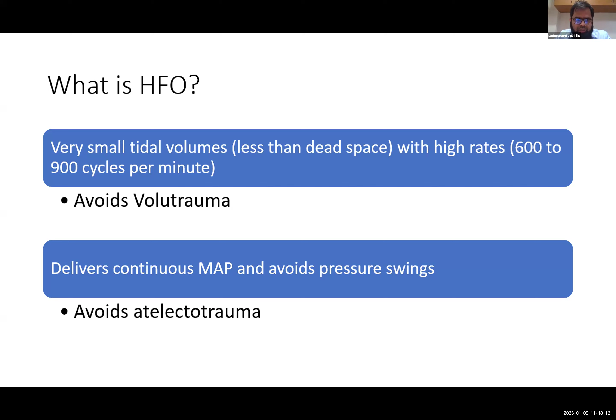So, the basic design and how it works. This is the basic design of the SensorMedics, but now a lot of ventilators are available, with different mechanisms. Here you can see one piston. One ventilator apparatus will give the continuous MAP, the mean airway pressure, which is nothing but the end-expiratory pressure for alveolar recruitment and lung expansion, and on top of that you are using this piston pump to push the air into the respiratory tract. This forward motion will push the air in, and the backward motion will pull it out. So both inspiration and expiration are active, controlled by the piston pump.